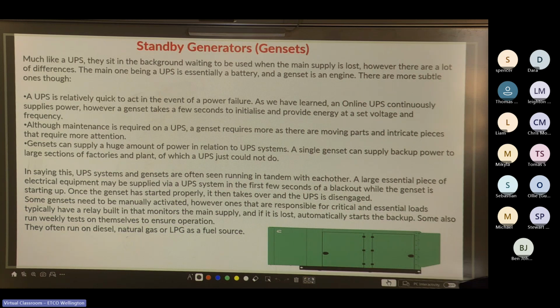The main switchboard has a PLC controlled breaker system so that as the generator comes on and starts to provide power, it will slowly bring on different loads for different areas of the hospital, starting with most critical to least critical until the generator is fully loaded, and then it will not provide any more power. That way they know computer systems, operating theatres, the ICU, the cath labs all have power before they start bringing power on for the patient areas where there's less critical patients.